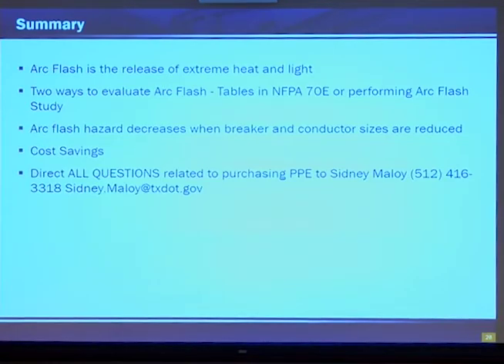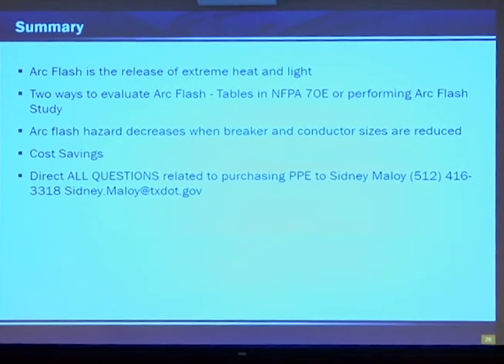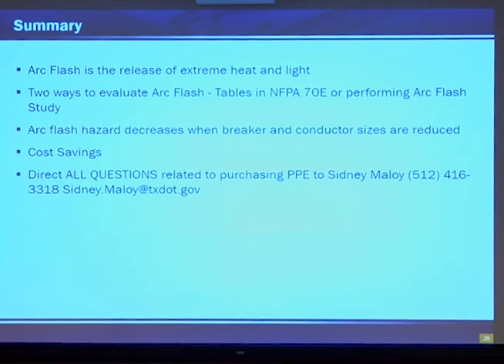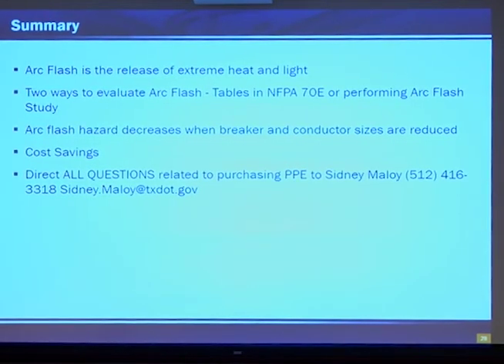To summarize, arc flash is the release of extreme heat and light. There's 2 ways to evaluate arc flash: the tables in the NFPA 70E, or performing an arc flash study. Both of these will give us the answer we need, what levels of PPE were needed. Arc flash hazard decreases when breakers and conductor sizes are reduced. The conductor sizes will also see a cost savings. But the main thing is PPE levels are needed and PPE needs to be purchased.